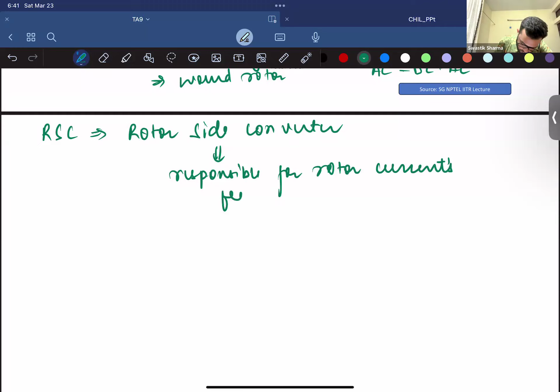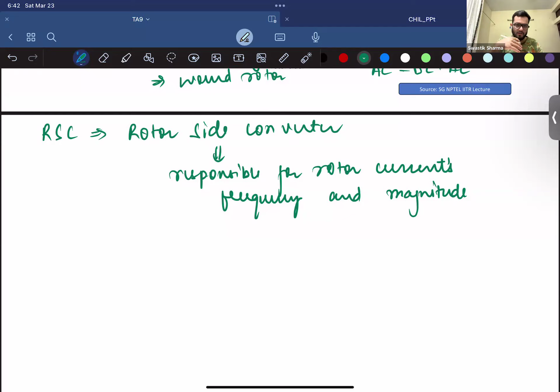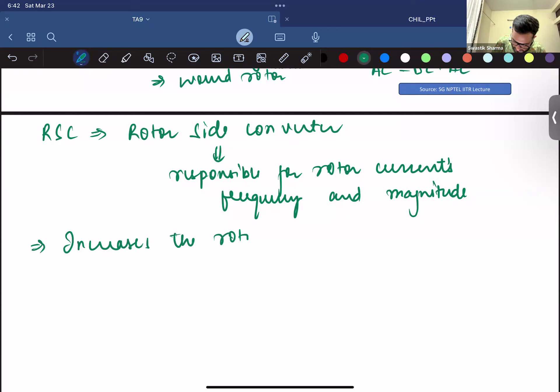So it's used to control your rotor, because at the end of the day, how your rotor behaves at low speed and high wind speed is what tells you how it should behave in the first place. What we want is for the output of the stator to be at a constant frequency, regardless of how the wind speed behaves. This rotor side converter provides control, which is given as it increases the rotor speed - I'll explain every detail, but I'm just giving a brief overview.